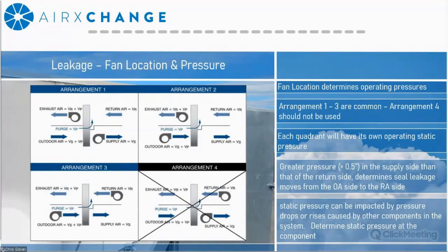Each quadrant is going to have its own operating static pressure. And in general, what you're trying to determine is that the pressure scheme naturally wants to move the air from the supply side to the exhaust side. So as a typical rule of thumb, you're going to want to have roughly a half inch or greater static in the supply side than in the exhaust side. And some of these fan arrangements provide this a little bit easier than others.